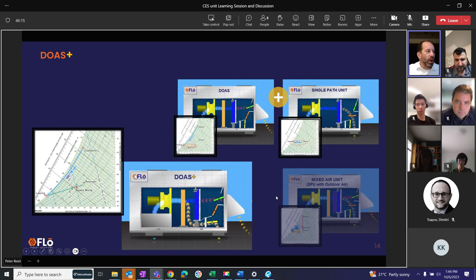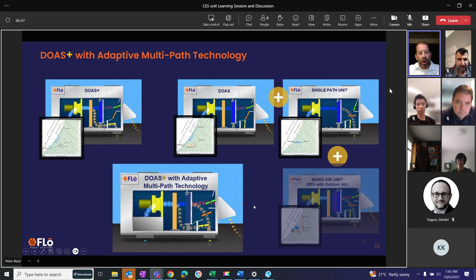Now, what that means is we're getting less dehumidification capacity out of the coil because there's more air now going across it, but we're getting more sensible or cooling capacity out of the system as a whole. You can't have it doing all of those things at once. Fortunately, we don't need it to. So there's no psychrometric for this. Instead, I'm going to show you an animation on the next slide that'll explain how we use these different dampers in different operational modes. And that'll be this next thing.